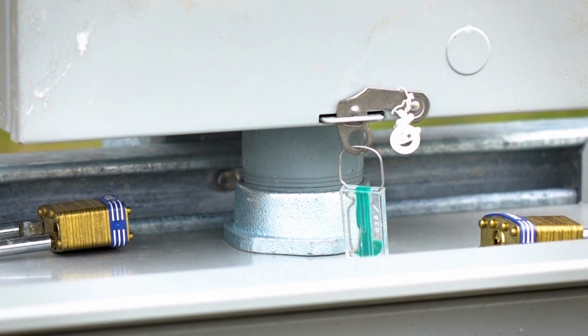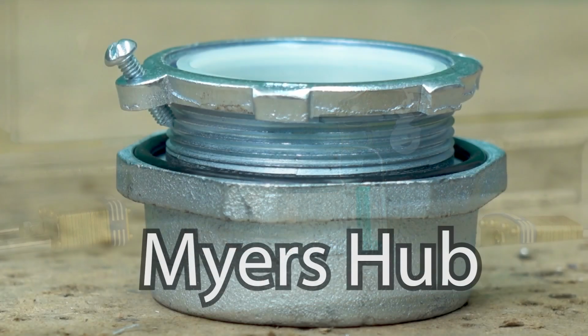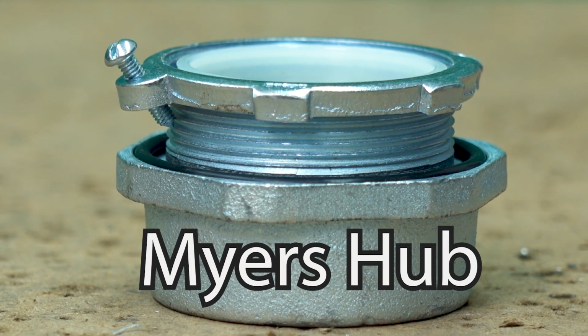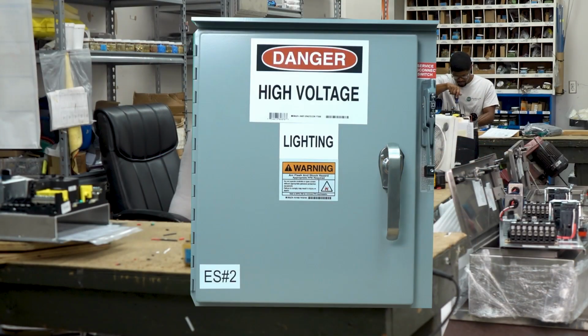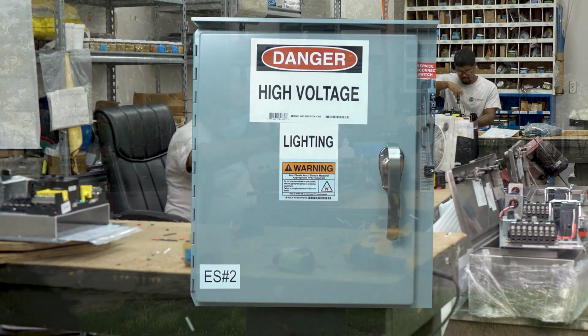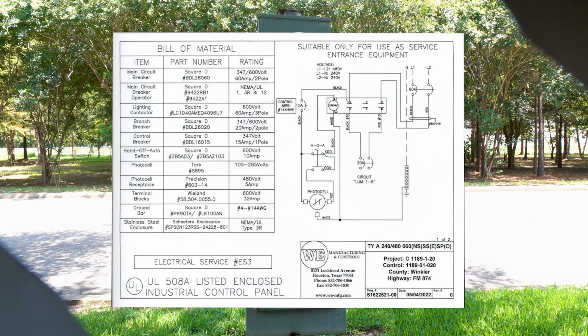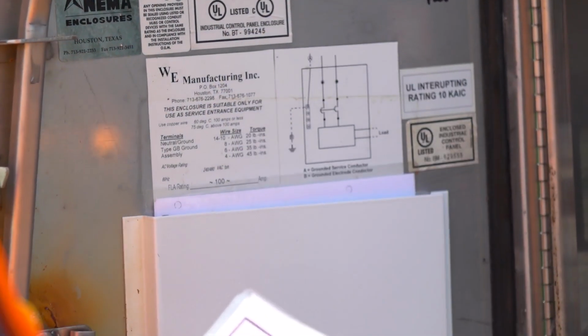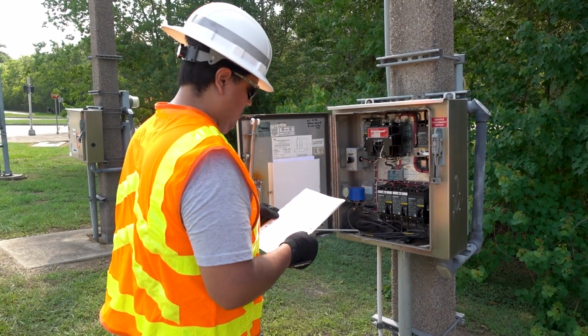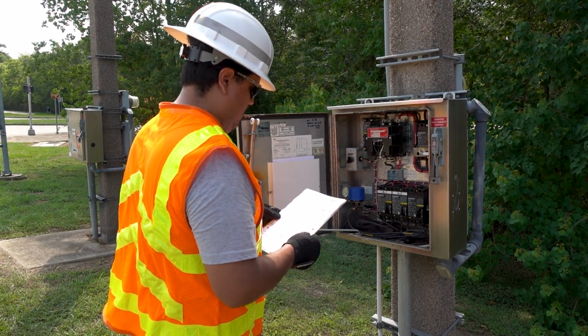For any electrical enclosure located outdoors, conduit must be installed so that water will not enter the enclosure where the connections are made. TxDOT requires that a watertight threaded hub, or Myers hub, be used for the top conduit coming into the service. The metal service enclosure, which contains the working electrical parts, will be the next item we will inspect. This portion of the electrical service can be correctly inspected by using the line drawings from the UL 508 manufacturer, typically located in the data pocket of the electrical service enclosure, and with the electrical service data chart, which is in the plan set.